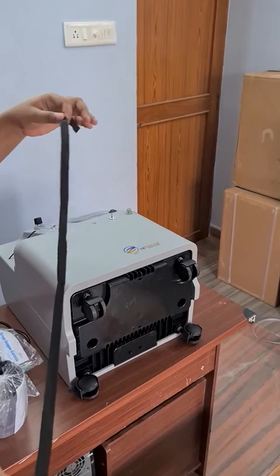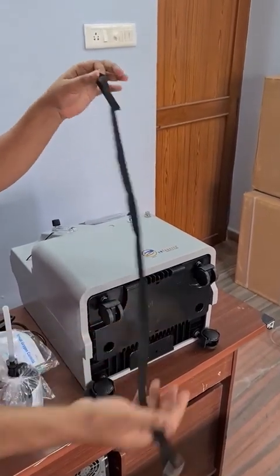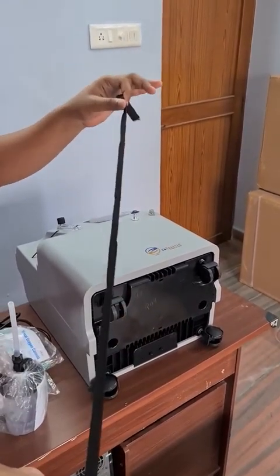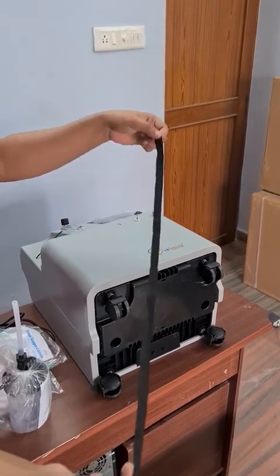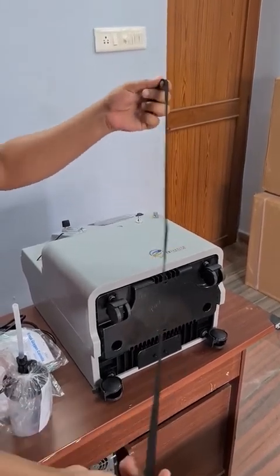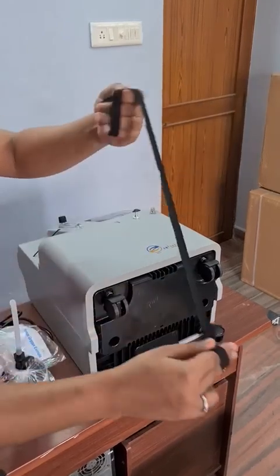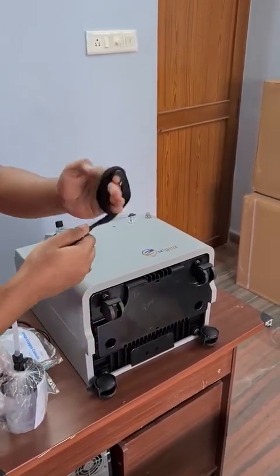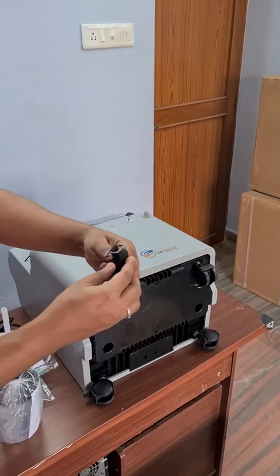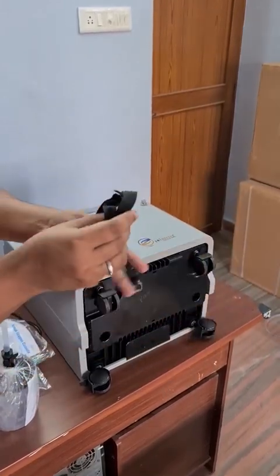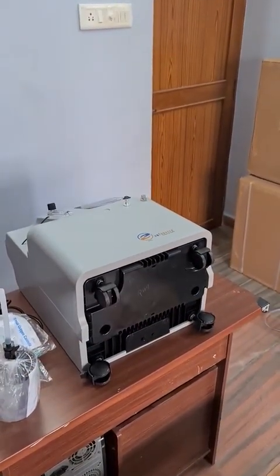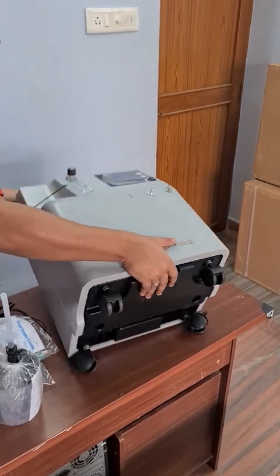So this tag has to be either removed, or you have to cut it and take it outside before you switch on. If you run the concentrator along with this tag, it may damage the compressor. This tag is mainly given in order to protect the compressor during transport. Now that I have removed the tag, I am going to keep it aside, and let's go ahead with switching on the concentrator.